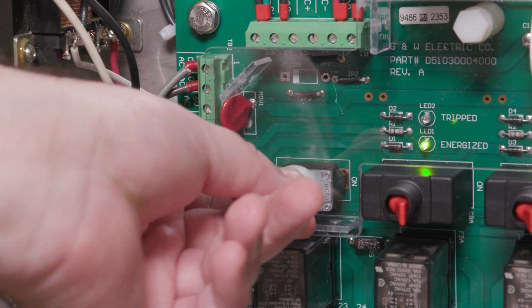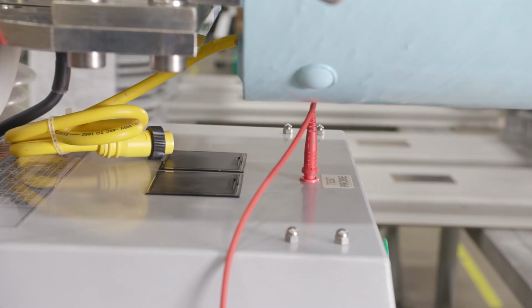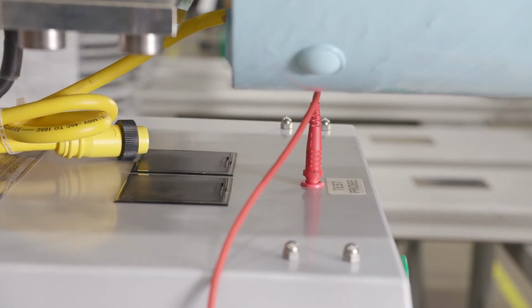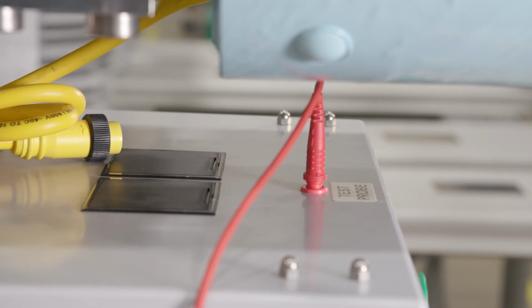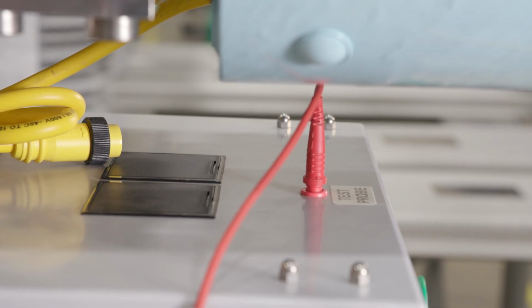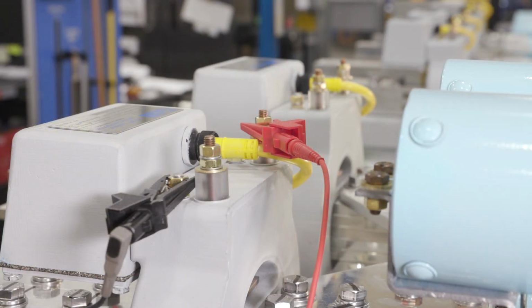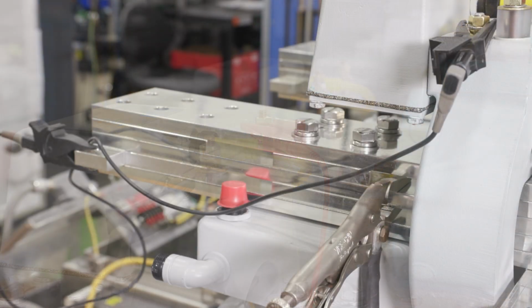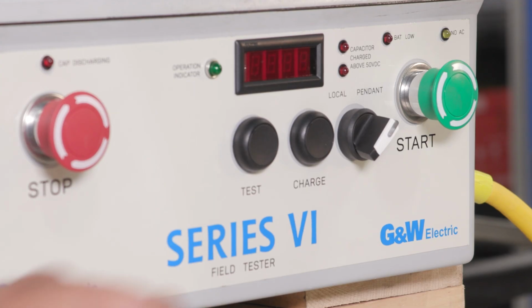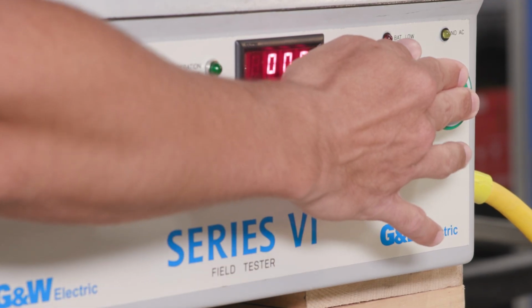Energize the control box. Now use the red patch cord supplied with the field tester to connect the tester to the SFL. Insert the banana plug into the receptacle on the face of the field tester box. Connect the alligator clip end to the insulated tall terminal on the SFL. Next, connect the black patch cord with alligator clips across the uninsulated short terminal of the SFL and the bus bar. Push the start button to turn on the tester.